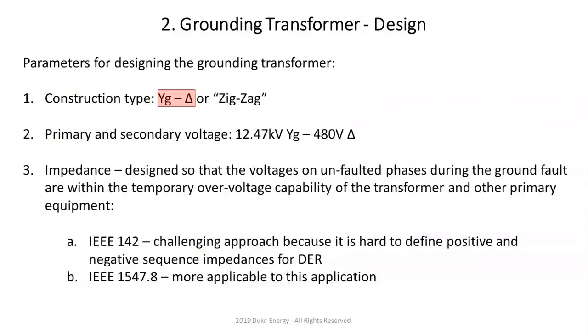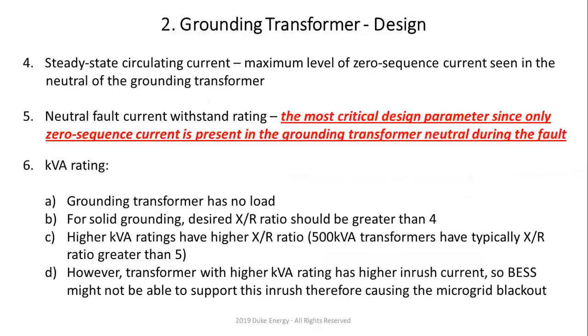This is really important because when you have a line-to-ground fault on the system inside island mode, the phase-to-phase voltage on the two unfaulted phases prior to the fault, if you multiply that by 0.8, has to be greater than those same phase-to-ground voltages after the fault. So this grounding transformer is probably the most challenging part, like I was telling you, right?